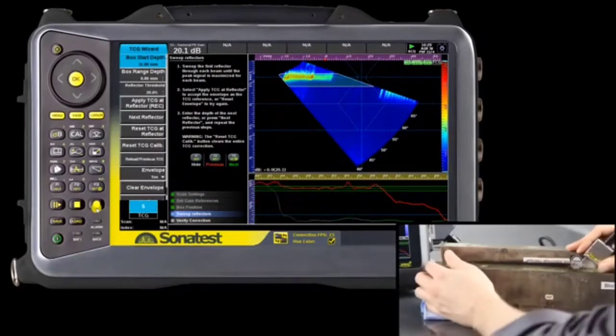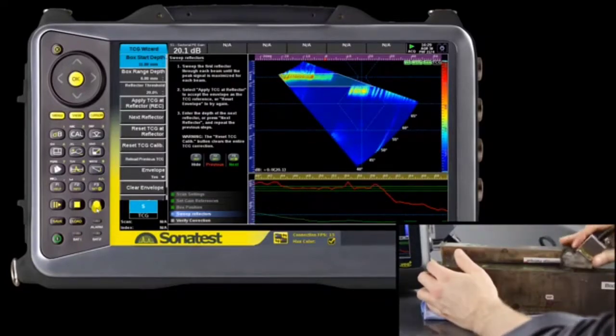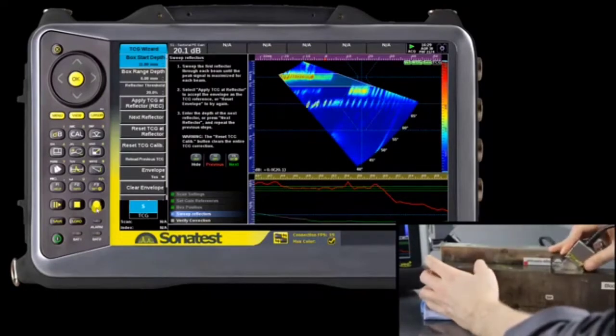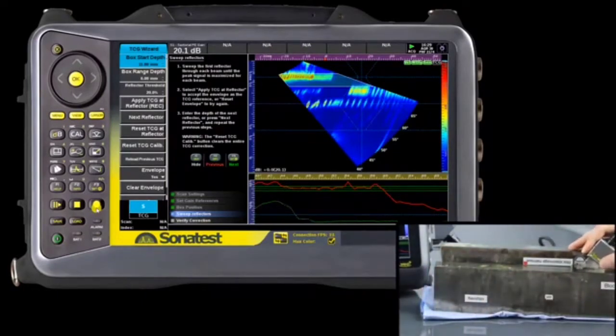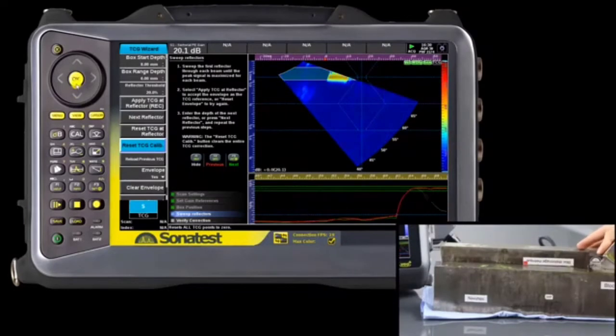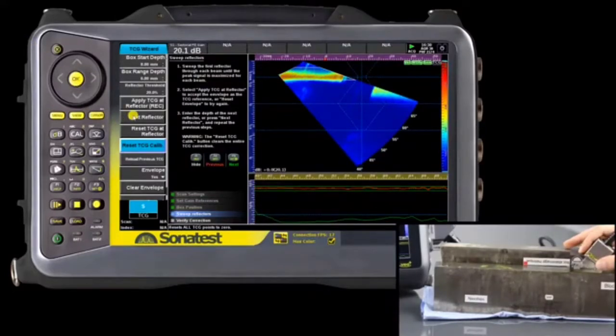In case of bad manipulation, the gain compensation could worsen the signal. In this case, there is an option called Reset TCG Calibration, which cancels the gain correction. The coupling and the probe orientation between the wedge and the part are crucial parameters. If inconsistent, it will be necessary to repeat the process. It helps if you use a guide for your probe to ensure the probe and block orientation remain stable during the sweeping step.